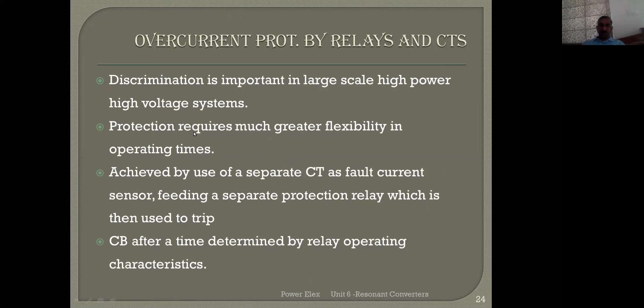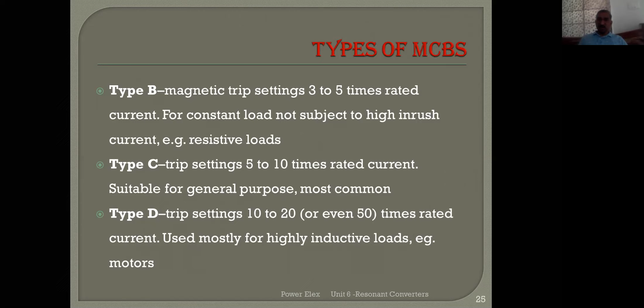The types of MCBs we have are type B, C, and D. B has a magnetic trip rated at 3 to 5 times, C is 5 to 10 times, and D is 10 to 20 or even 50 times the rated current. We usually install these at power line distribution areas carrying current from the mains to our labs, offices, classrooms, industry, etc. Along with MCBs, we have MCCBs, moulded case circuit breakers, and air circuit breakers, so that our circuits, systems, and other loads get protected from temporary overvoltages and overcurrents. This is all we have to take care of for the circuits and systems. So just go through this material and revise it.